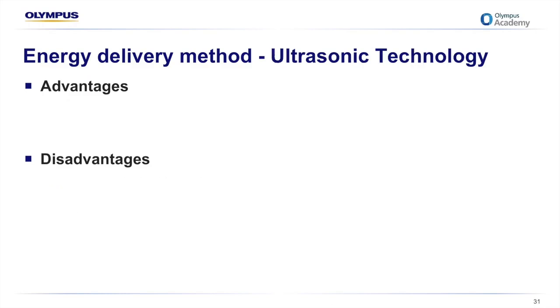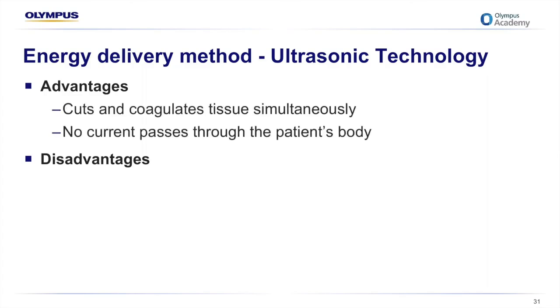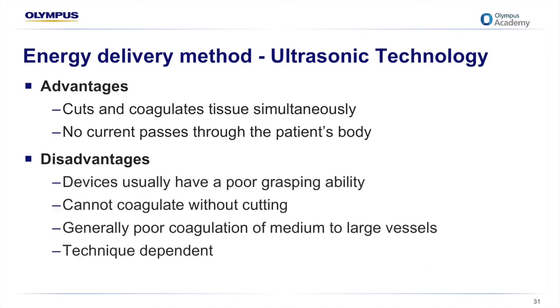Ultrasonic energy, although not electrosurgery because electrical current doesn't pass through the patient's body, is also mentioned here because we now have some devices or a device which incorporates both ultrasonic and bipolar technology in the one device. The advantages of this is it cuts and coagulates tissue simultaneously, and as mentioned, no current passes through the body. However, this can also be a disadvantage because, especially in the larger vessels that you want to seal, if you're cutting and coagulating at the same time, you're potentially not achieving a reliable and consistent seal.